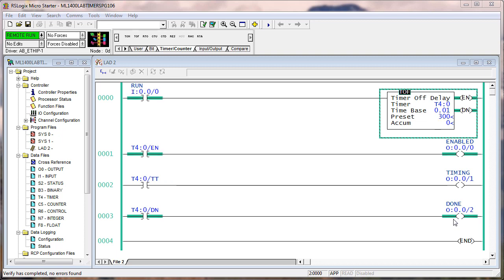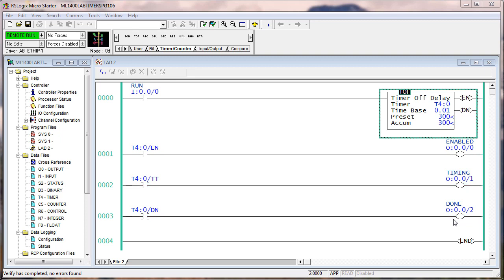It just so happens we're turning on output two just so you can see it on your simulator. So I'm going to turn this back on, enabled and done bit are on. But I'm looking at output two on my digital field device simulator. If I turn off input zero, the timer timing pulse is lit. And then both the timer timing and the done bit go off three seconds after I turned off the run bit.